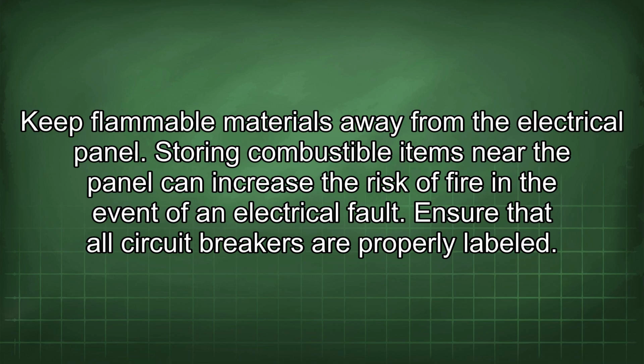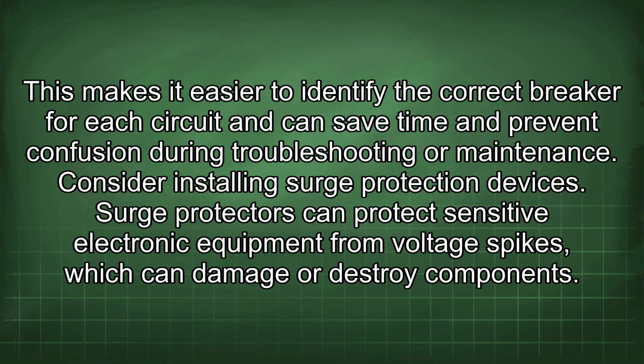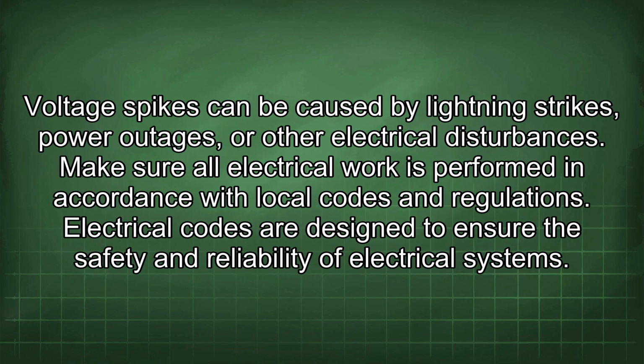Ensure that all circuit breakers are properly labeled. This makes it easier to identify the correct breaker for each circuit and can save time and prevent confusion during troubleshooting or maintenance. Consider installing surge protection devices. Surge protectors can protect sensitive electronic equipment from voltage spikes, which can damage or destroy components. Voltage spikes can be caused by lightning strikes, power outages, or other electrical disturbances.